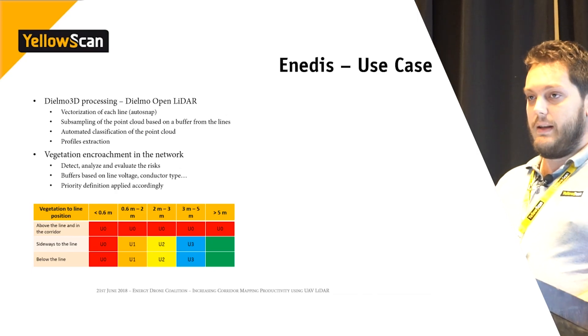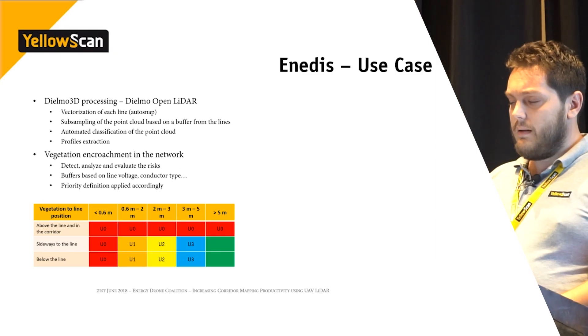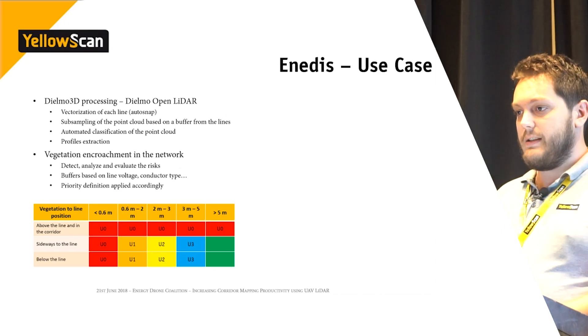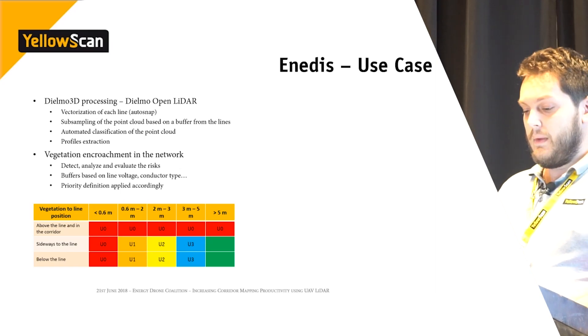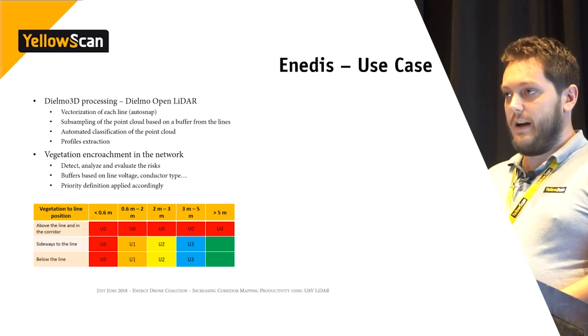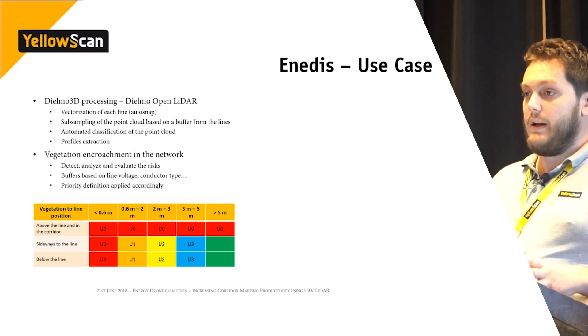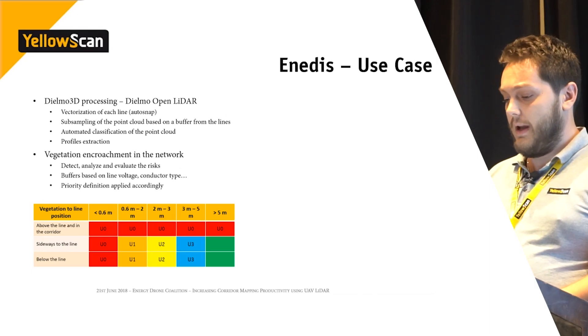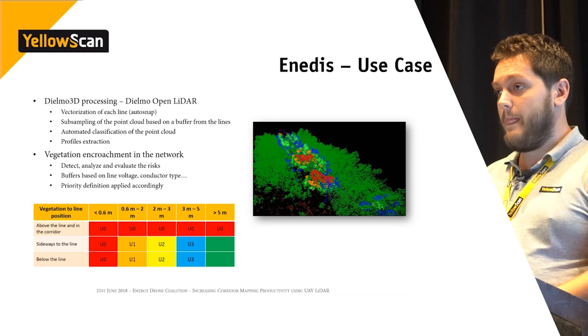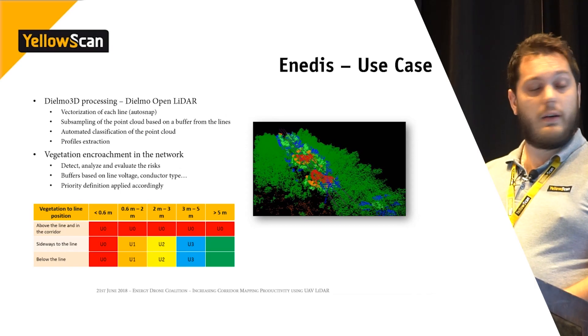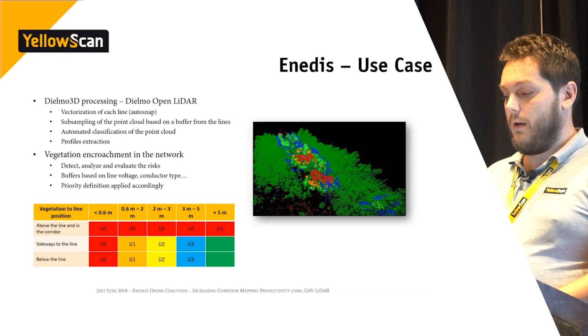The first result provided was vegetation encroachment. You want to detect and analyze risks around your power line based on voltage. Enedis defined a chart of the distance to the power line depending on the situation of surrounding vegetation. They produced a global mapping and a color-coded point cloud based on the risks the vegetation posed relative to the power line.